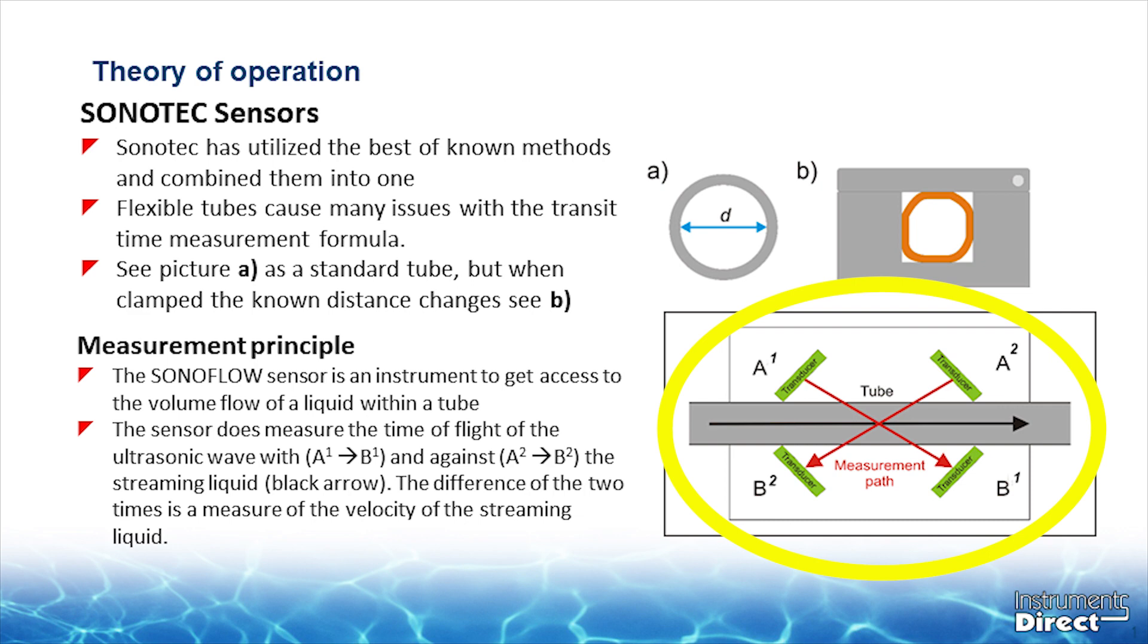As you can see in the diagram in the lower right-hand corner, the gray represents a flexible tube with the liquid flowing from left to right. Four piezo elements are arranged in an X pattern. The transmitter sends pulsating ultrasonic waves in a predefined frequency from one side to the other. So A1 sends a signal to B1, and it's going in the direction with the flow, and the transit time is noted.